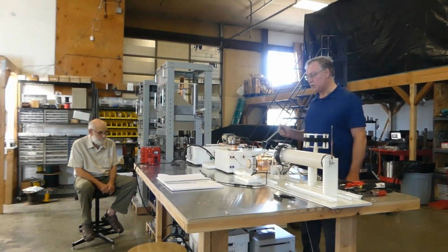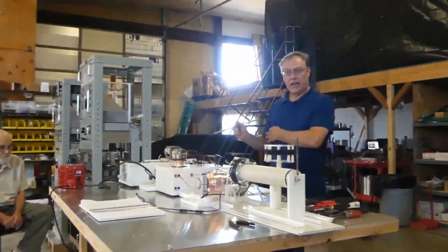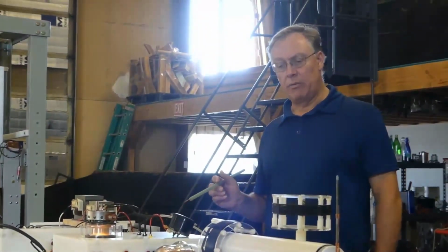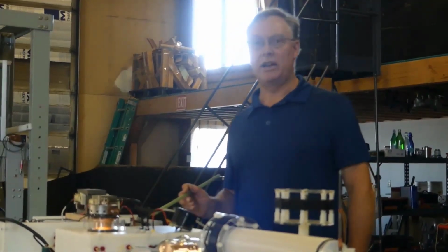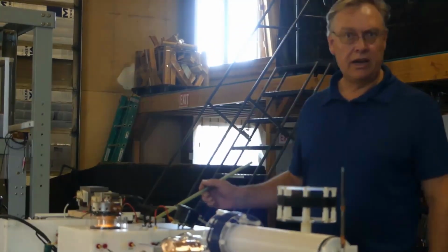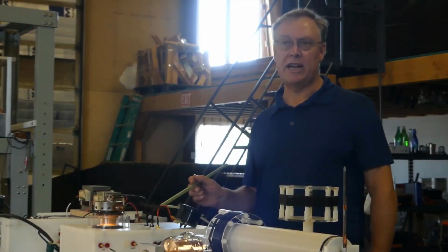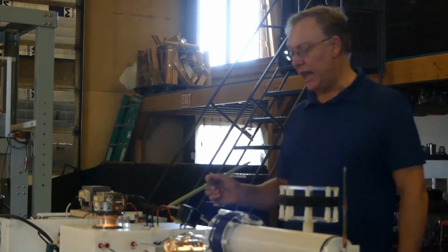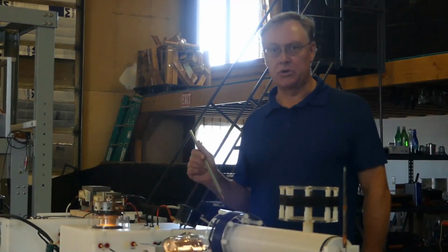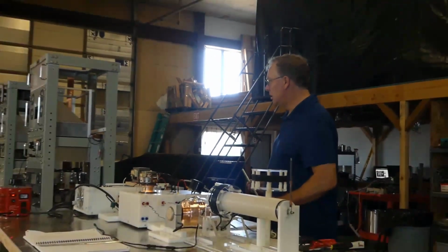And then just to add, what we did to initially test that system was we first of all measured the open circuit cathode voltage to make sure that is not too much for the relays. So all that means is disconnecting one side of the cathode from ground and measuring that open circuit voltage on the cathode to ground, which we measured with everything set as it would be when you were running. That measured at 158 volts. What is really the maximum that the relays can take? I wouldn't go above 300. Above 300.